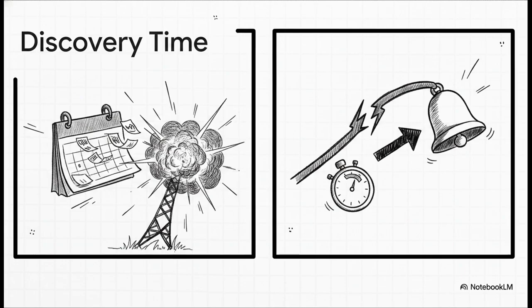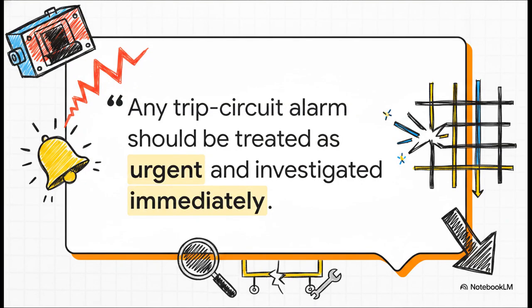In an unsupervised system, you're going to find out when the next scheduled test rolls around or, way worse, when a real fault occurs and the breaker just straight up fails to clear it, leading to a massive outage or catastrophic equipment damage. Now contrast that with a system running TCSBR. The very instant that wire broke 2 months ago, that tiny 1.5 milliamp test signal dropped out and an alarm was triggered within seconds. And that leads us to a completely non-negotiable operational takeaway.